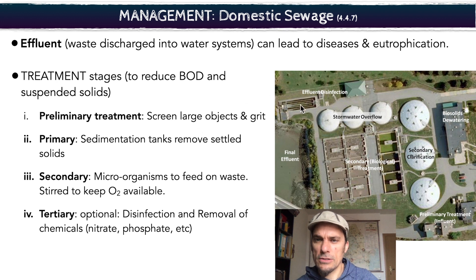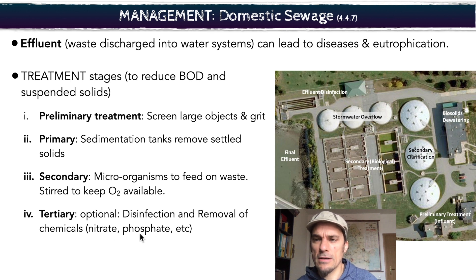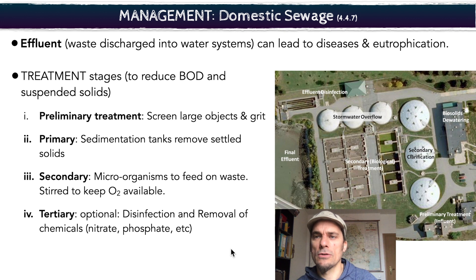Here's a tertiary treatment over here. So effluent disinfection — you can have disinfection for pathogens, for example. You can also have removal of chemicals if there's high nitrate or phosphate content in that water, because you don't want those nitrates and phosphates moving into the water system, as that will cause eutrophication.